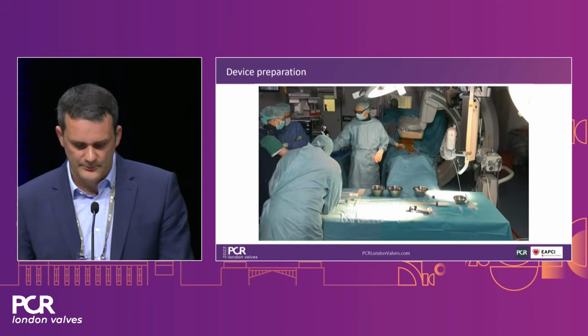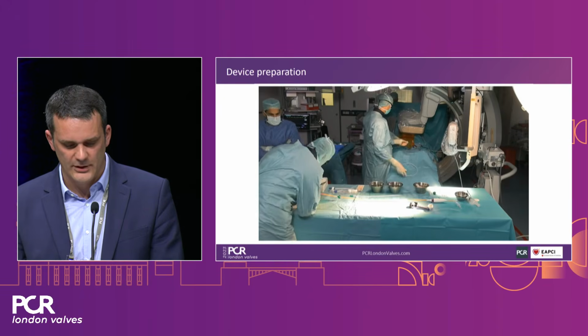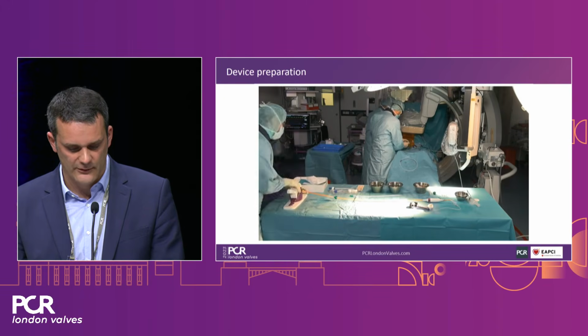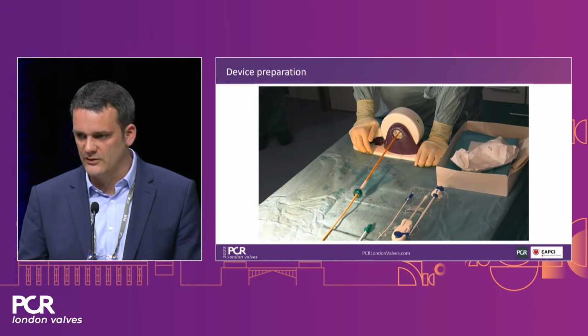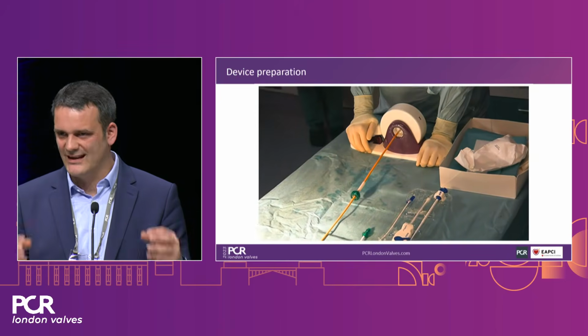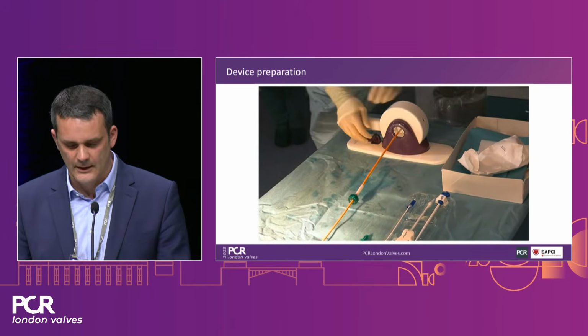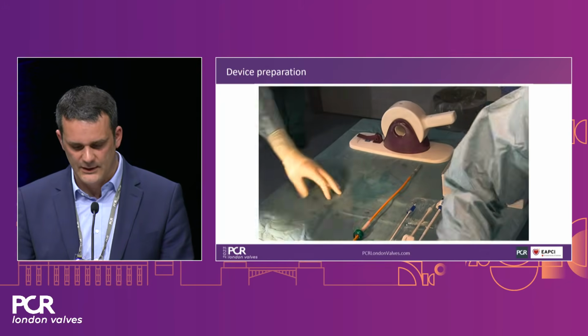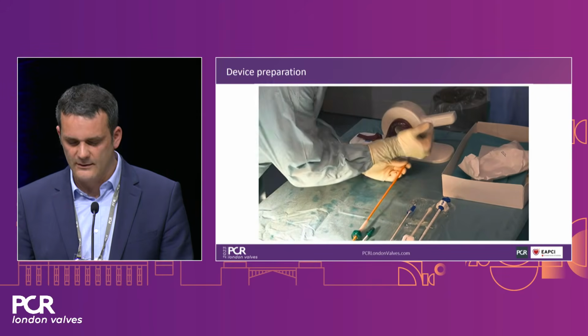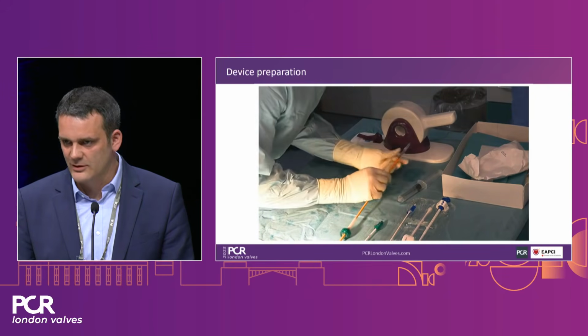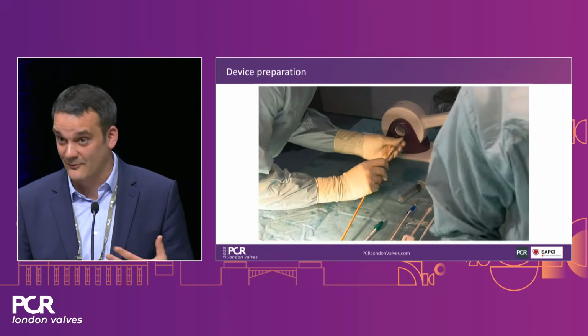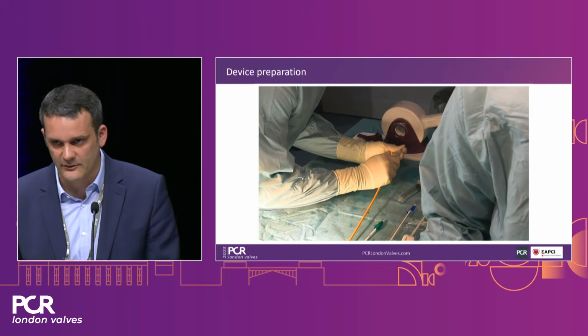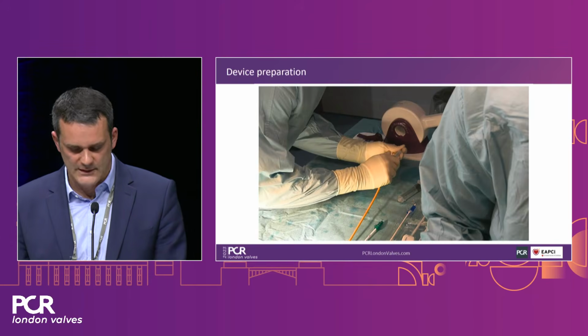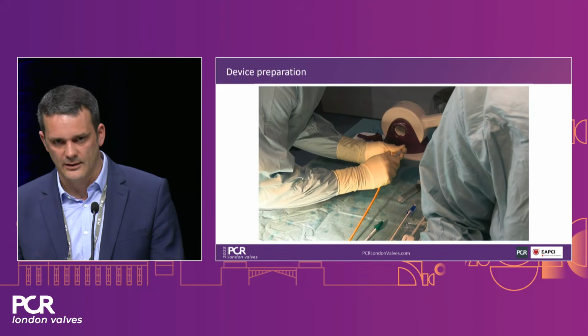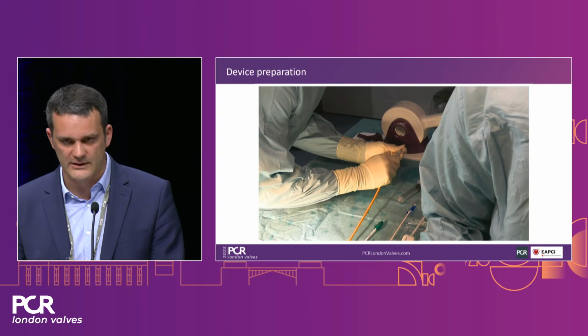While we do so, there is some footage of the device preparation here, which is done in parallel, of course. It's basically a straightforward process, the crimping. The valve is directly crimped in between two conical structures inside the balloon. They're called stoppers by the company. And the valve is crimped in there with the device. Easy to learn, which is, I think, good for the staff shortage that we face in our days. So basically it's a system that also the physicians can crimp themselves at night when you face emergencies or however. Quite a good system. In the end, you have a loader that is sheltering the valve while inserting it into the hemostatic valve of the sheath.